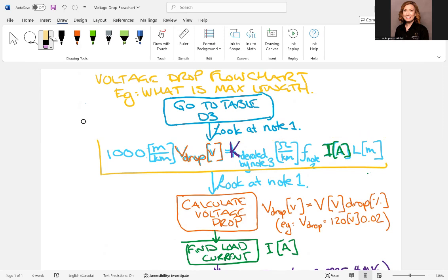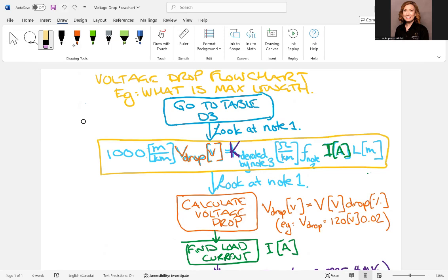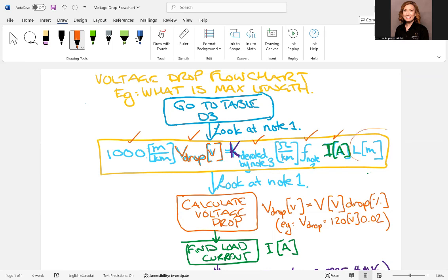So now we've done 1,000. We know that. We know the voltage drop. We could find K and derate it accordingly, according to temperature. We can find F from our notes. It's usually two. We know the current that we're working at. And we can solve by rearranging this equation, solve for what is the maximum length. Or you can do any number of calculations if you just rearrange this in a different manner.